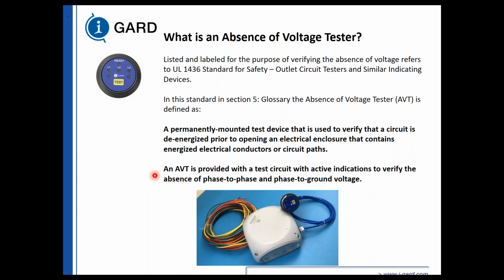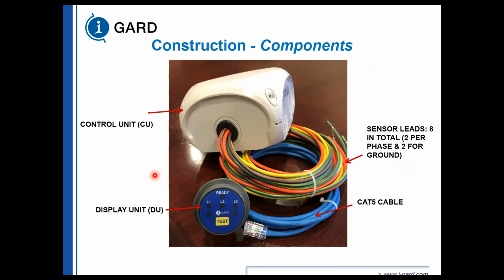So here's a device that you can test before you open up any doors and before you apply any test probes into the cell, where most people were getting hurt, that can verify the absence of voltage. And it looks like this. The i-Gard absence of voltage tester has a control unit, wire, 2 per phase and 2 for ground. So we have to put in 2 wires per phase and ground to verify that the actual unit is connected.